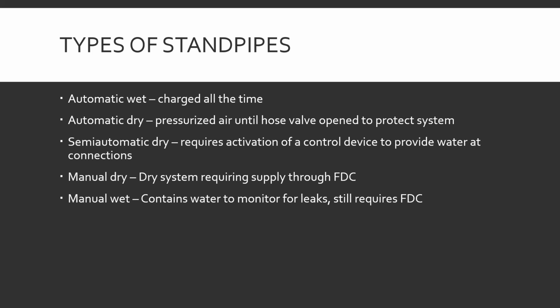Pressurized air until the hose valve is open to protect the system. That's kind of like, these two are like our wet versus dry sprinkler systems. One has water in it all the time. The other has air until you want to flow water. Semi-automatic dry. Requires activation of a control device to provide water at the connections. That's like our pre-action one. So if you go up and you open the valve, it's not going to do anything. Something else has to tell it, okay, we need water in the system, let water out of the system.